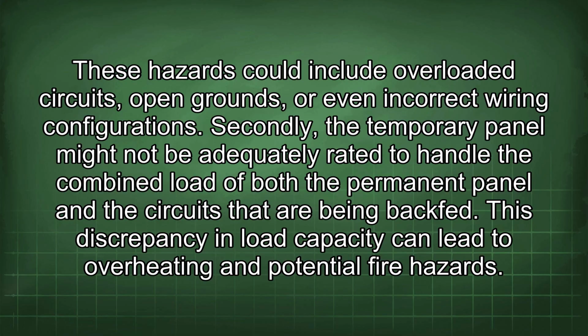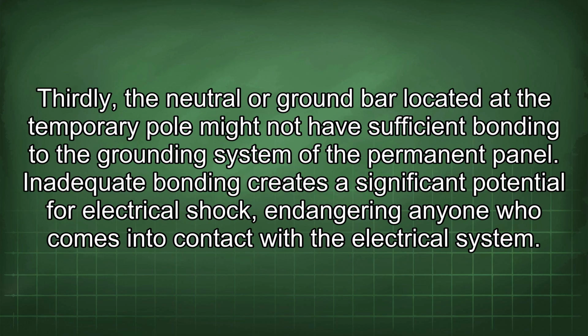Secondly, the temporary panel might not be adequately rated to handle the combined load of both the permanent panel and the circuits that are being backfed. This discrepancy in load capacity can lead to overheating and potential fire hazards. Thirdly, the neutral or ground bar located at the temporary pole might not have sufficient bonding to the grounding system of the permanent panel.